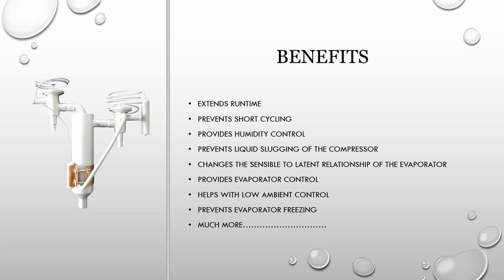Prevents liquid slugging. With a TXV valve in place, it only sees superheat, but with a fixed orifice, what you'll end up having is that you could have slugging because the superheat's depending on the load and the charge. And when the load goes away, the superheat goes away. This here maintains it.